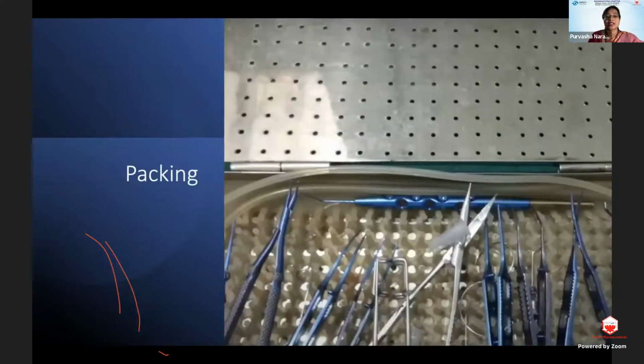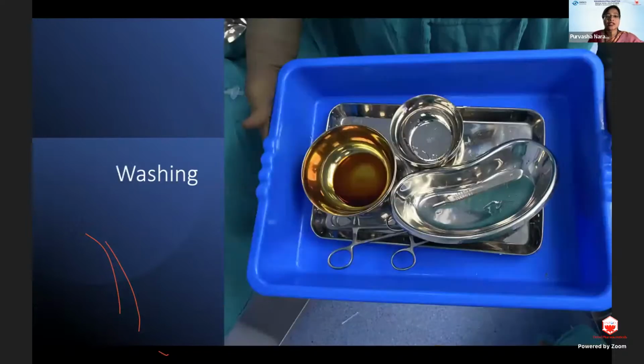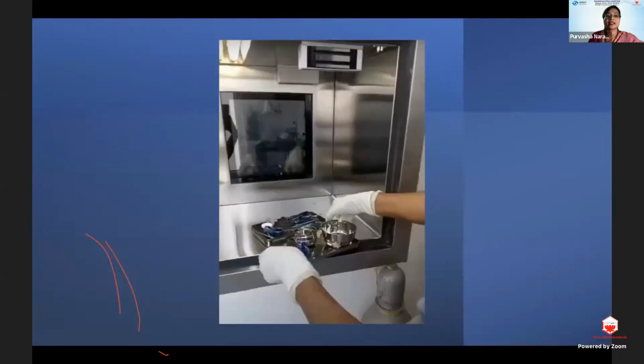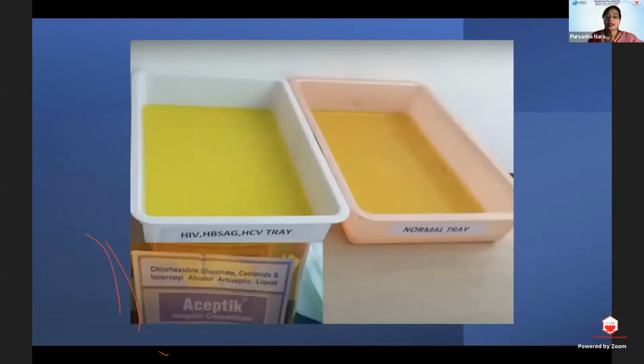Then comes the step of packing, where each instrument is placed back into the tray, and along with the rest of the instruments and the hollow tubes, we place the type 4 indicator or the type 6 indicator inside the tray. That is the first indicator that we place. The bigger instruments can go directly through the hatch box out, and then they are washed and packed in separate drums. That is how you have to clean and pack them.